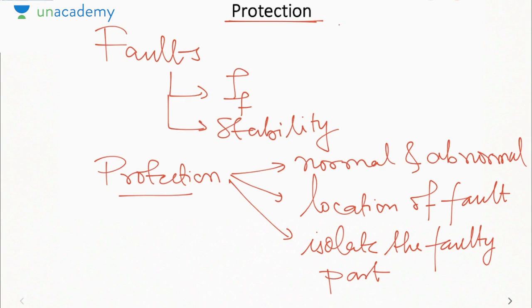Mostly the faults that we study are concerned with transmission lines. Okay. Now, why only transmission lines? The thing is that transmission lines always have bare conductors which are spread in the atmosphere or in the environment. Okay. They are exposed to the environment. They are exposed to the natural surroundings. Whereas, in the case of machines like generators and transformers, the conductors are usually shielded inside the outer covering of the machine. That is why chances of fault are very less. But in a transmission line, a tree branch can fall, or the transmission line may break down. In the event of a storm, the transmission line may break. So, there are various reasons for fault occurrence. So, most of the faults that occur are concerned with the transmission line.